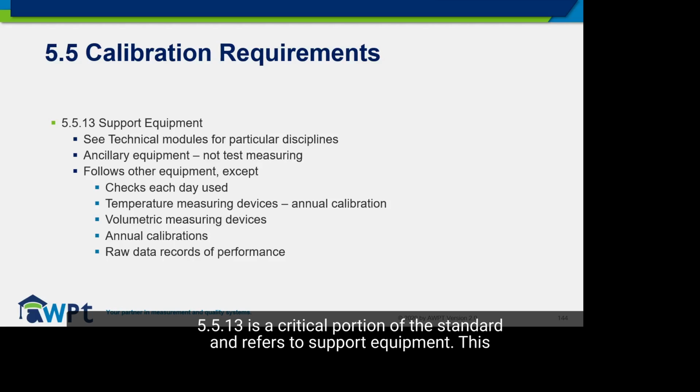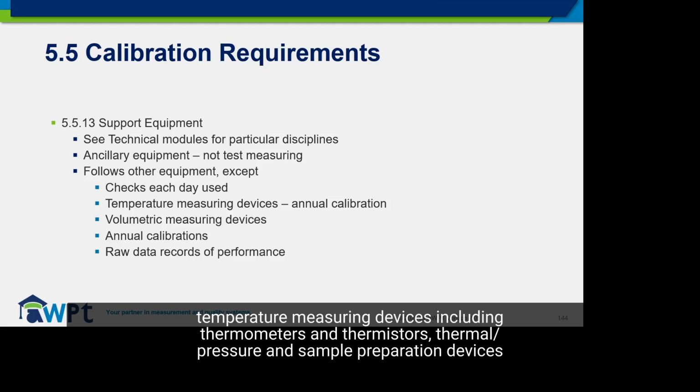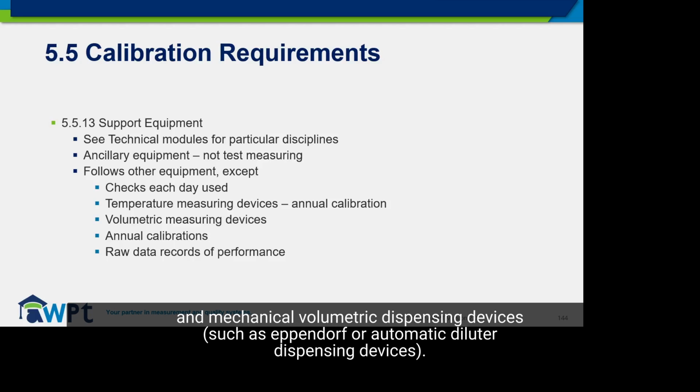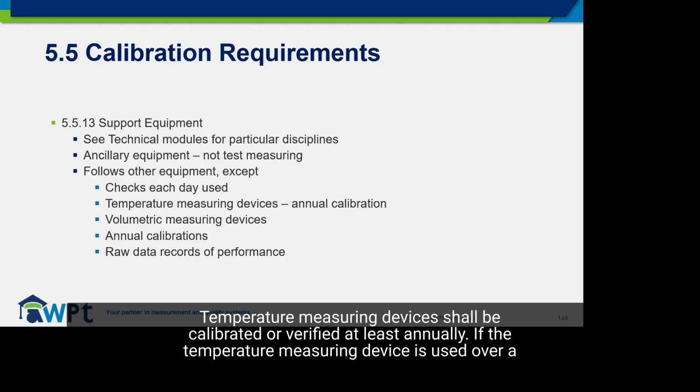5.5.13 is a critical portion of the standard and refers to support equipment. This includes, but is not limited to, balances, ovens, refrigerators, freezers, incubators, water baths, temperature measuring devices, including thermometers and thermistors, thermal pressure and sample preparation devices, and mechanical volumetric dispensing devices, such as Eppendorf or automatic diluter dispensing devices. On each day the equipment is used, balances, ovens, refrigerators, freezers, incubators, and water baths shall be checked and documented. Temperature measuring devices shall be calibrated or verified at least annually.